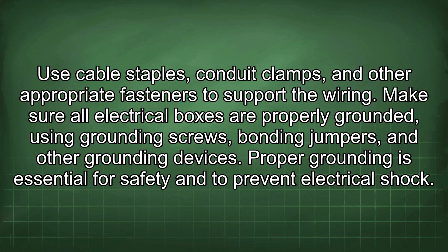Ensure that the wiring is properly sized for the anticipated loads, in accordance with the National Electrical Code, or NEC. Use appropriate wiring methods for the specific application, such as non-metallic sheathed cable for dry locations and rigid metal conduit for wet or hazardous locations. Secure the wiring properly to prevent damage or accidental contact. Use cable staples, conduit clamps, and other appropriate fasteners to support the wiring. Make sure all electrical boxes are properly grounded, using grounding screws, bonding jumpers, and other grounding devices. Proper grounding is essential for safety and to prevent electrical shock.